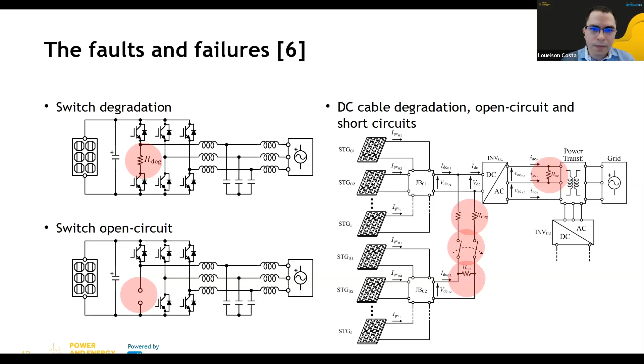We then simulated these multiple conditions for our inverter to see how it would behave. For the same day, we simulated multiple conditions: the real asset data, which we'll call the original data, and then DC cable degradation, open circuit, short circuit, switch degradation, and switch open circuit. What we can see here is that, for instance, we can easily spot the DC cable short circuit - let me get my pointer.